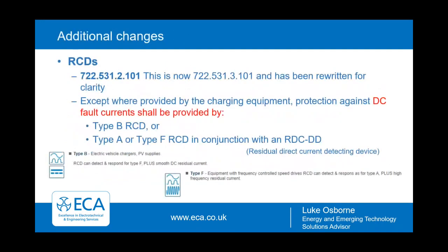Additional changes as well regarding RCDs. It was previously 722.531.2.101. It's now changed to what you can see on your screen there, and it's been rewritten for clarity. It does also state that except where provided by the charging equipment, protection against DC fault currents shall be provided by type B RCD or a type A or type F in conjunction with an RDC-DD.